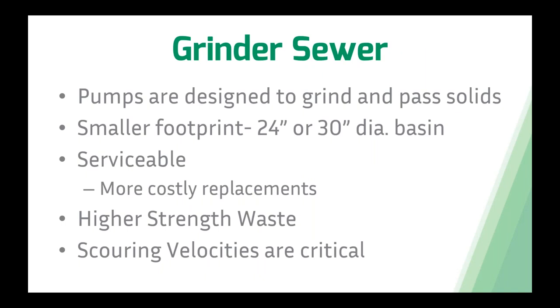Grinder pumps are designed to grind solids into a fine slurry and pass those solids into the collection system. Ground sewage is easier to pump than raw sewage, allowing grinder pumps to produce higher heads — much higher than a typical solids-handling pump. For pressure sewer systems, solids-handling pumps are generally not recommended because they have relatively low head capacities and significant fluctuation of flow rate. We stick with grinder pumps for raw wastewater pressure sewer systems.